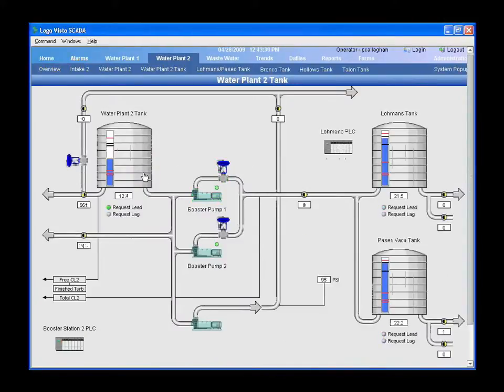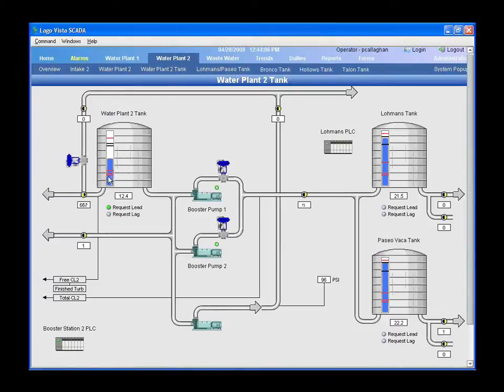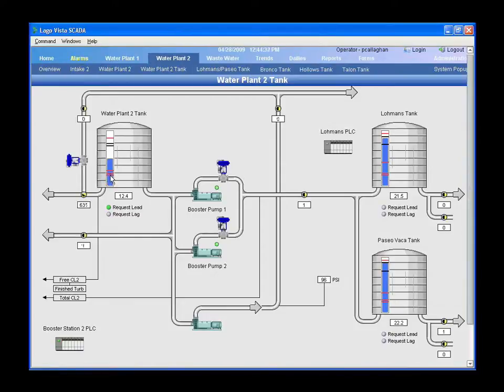All the tank images are pretty much the same and generic, which from an integrator standpoint saves me a lot of time in development. Through the actual tag created for each tank and all its associated variables, the image gets populated automatically — I don't have to do anything. We have tanks of different sizes; the hash marks show the levels: high level setpoint, low level, disable, return, start, stop — and these move based on whatever the setpoints are. Not all tanks have those setpoints, so when I create the group of tags for a tank, the image automatically knows which setpoints that tank has and displays them without any input from me.